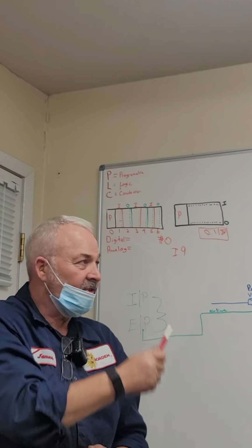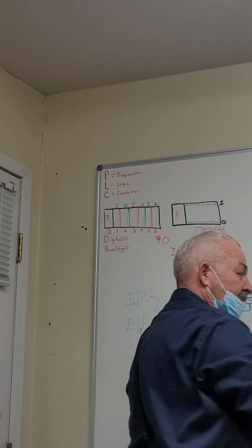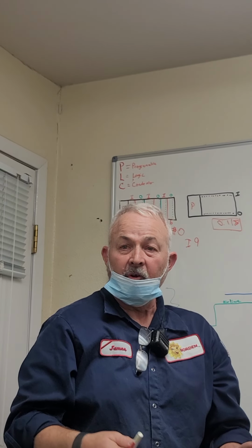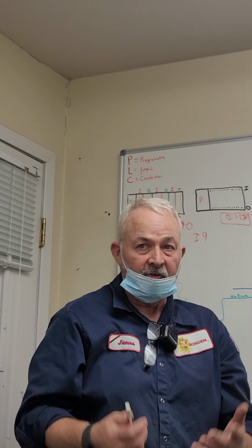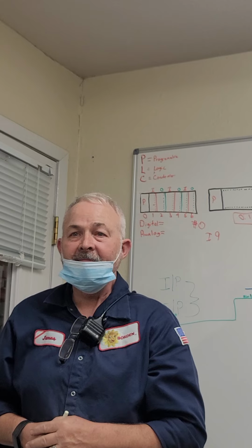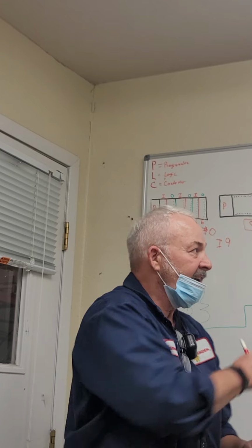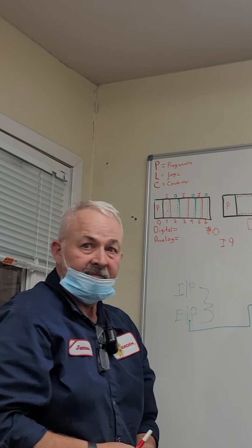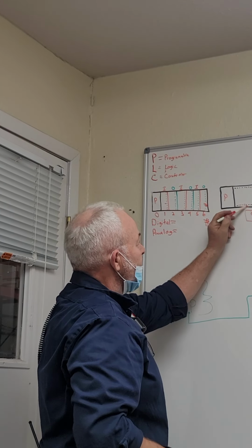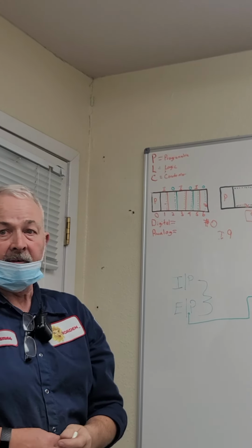There's something that's telling that program not to start. On the palletizer, we're out there trying to figure out what's going on with the proximity switch. There's something telling that machine not to start, something telling that machine to stop. Last week when we were working on that, remember? It was the gate that was open on the side, the safety switch. There's always something there, guys. It's nothing internal to the PLC. Now, you can have a channel fail, but very far and few between.